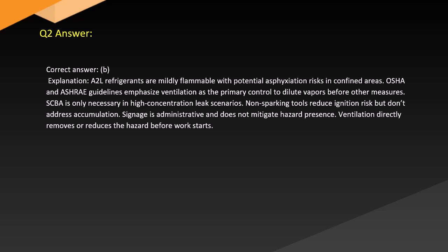Answer. Correct answer, B. Explanation. Refrigerants are mildly flammable with potential asphyxiation risks in confined areas. OSHA and ASHRAE guidelines emphasize ventilation as the primary control to dilute vapors before other measures. SCBA is only necessary in high-concentration leak scenarios. Non-sparking tools reduce ignition risk but don't address accumulation. Signage is administrative and does not mitigate hazard presence. Ventilation directly removes or reduces the hazard before work starts.